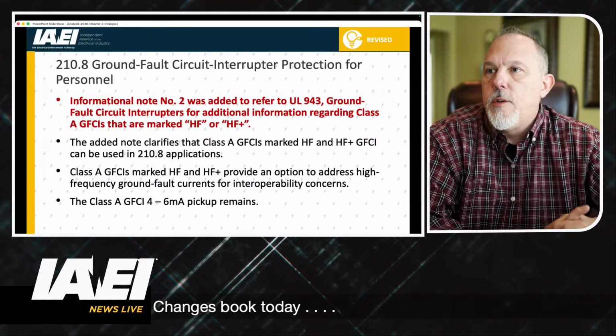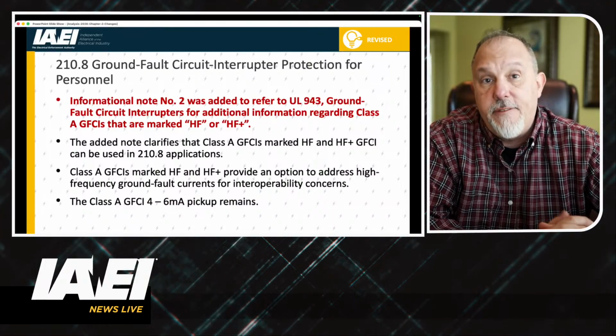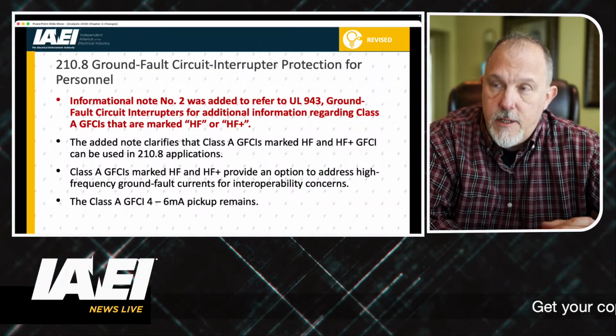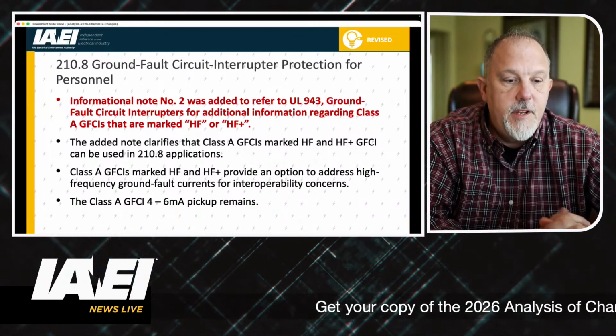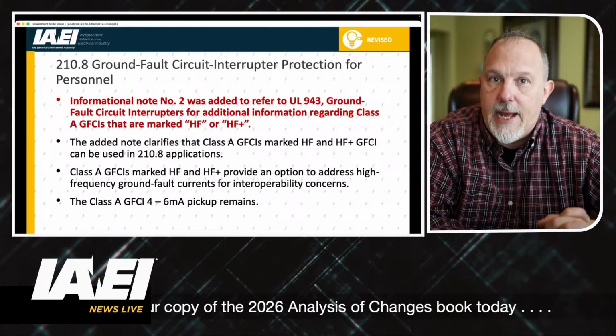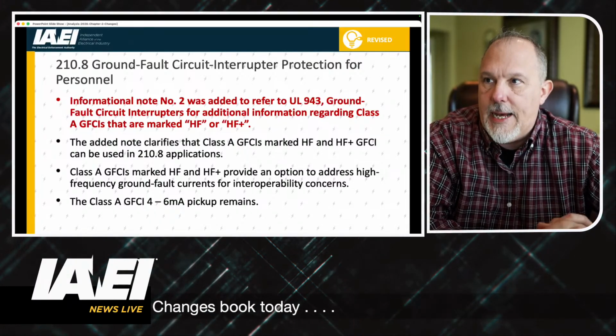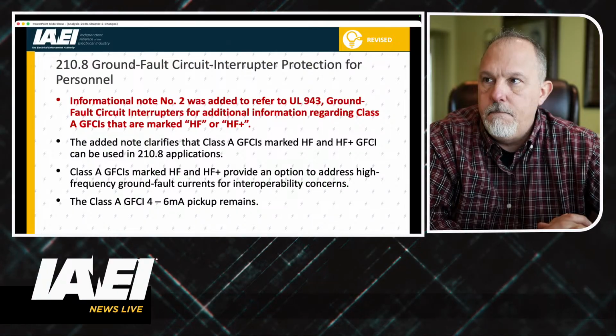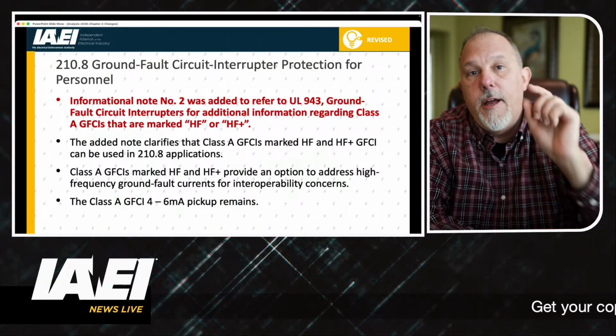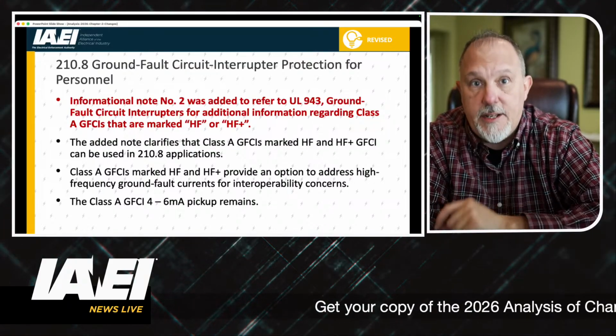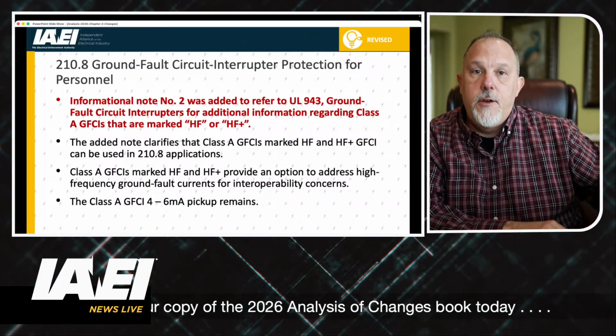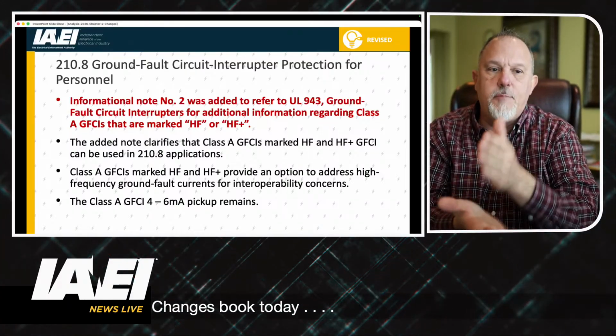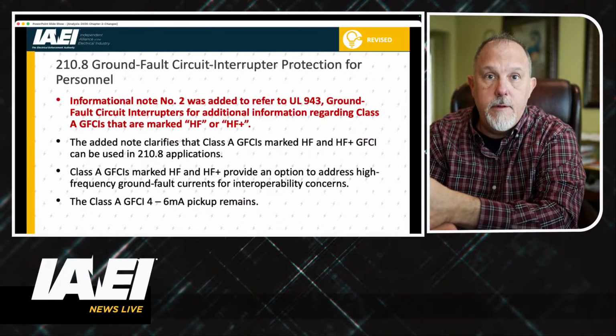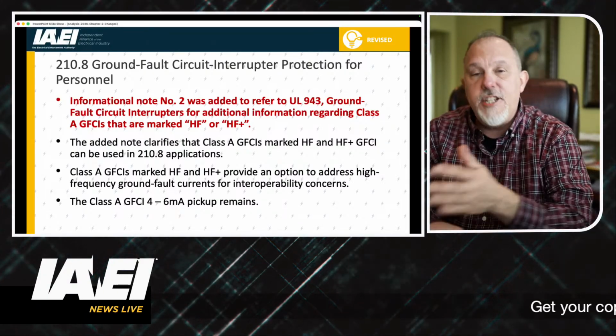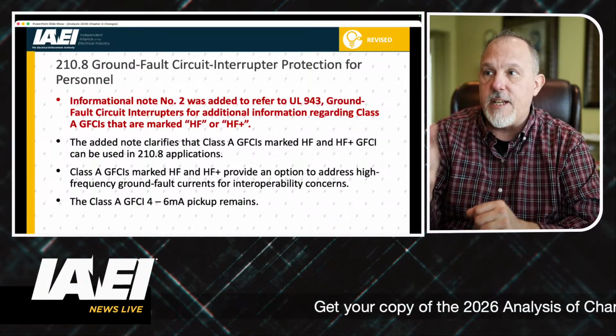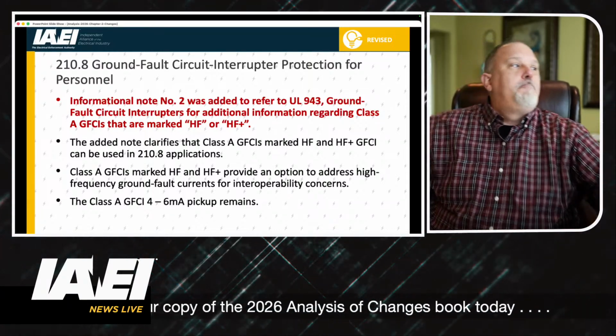Informational note number 2 is related to the HF, high frequency. Now the HF plus, the changes to UL 943 for HF plus, did not pass the mustard. They didn't pass committee. Now, a manufacturer can make an HF plus, it will still pass. So the way I would explain it is the HF plus is more restrictive than the HF.